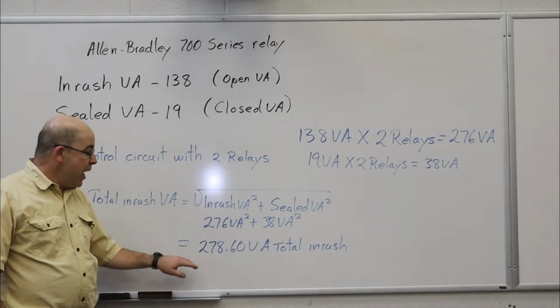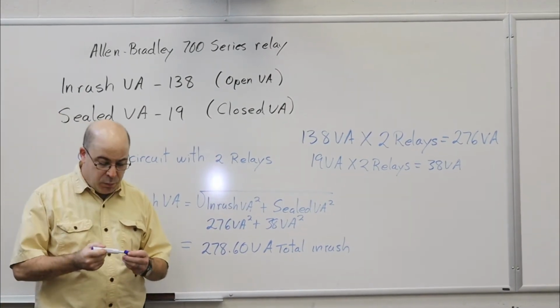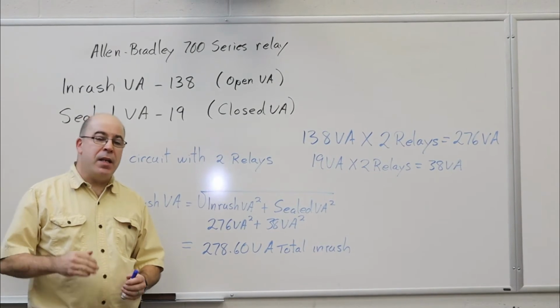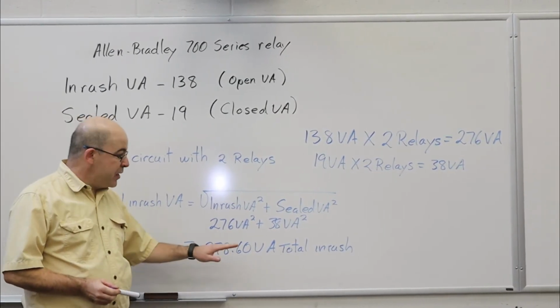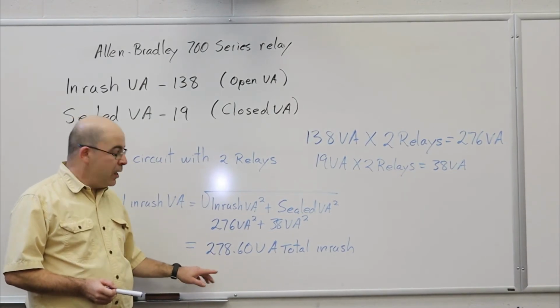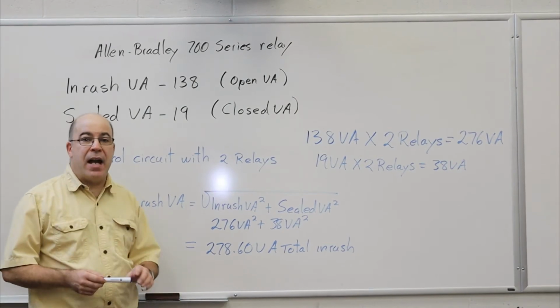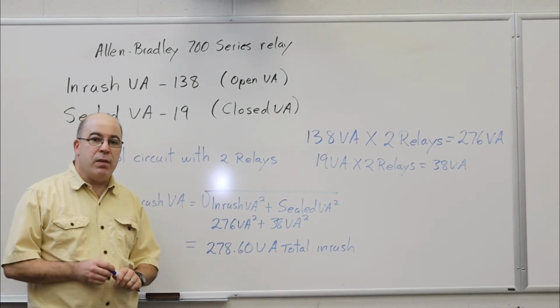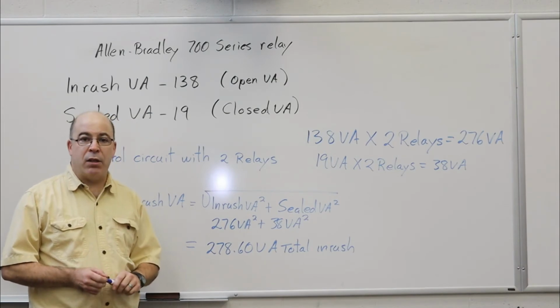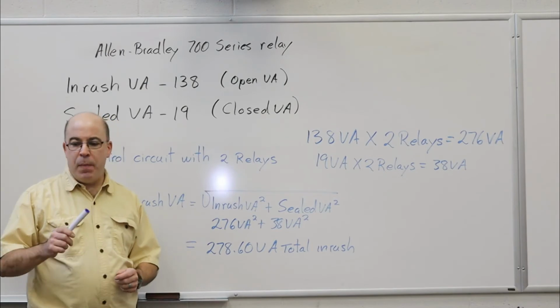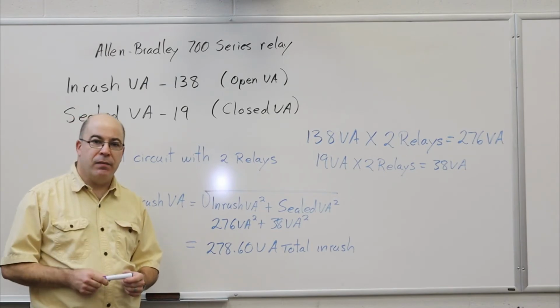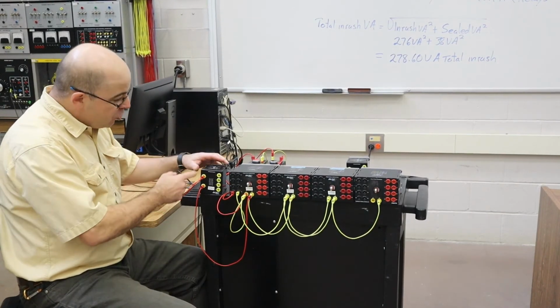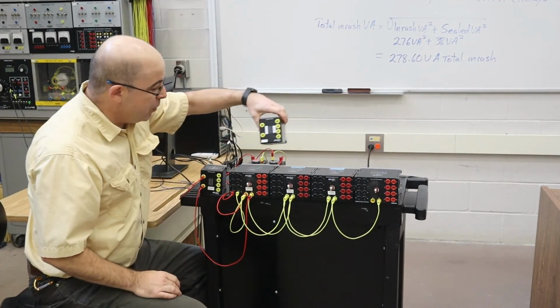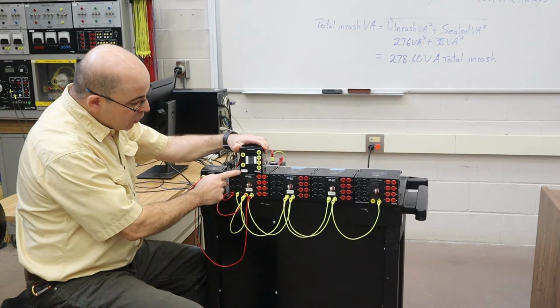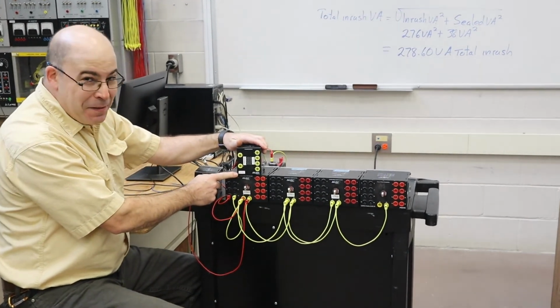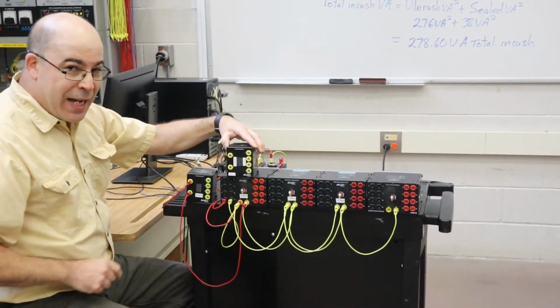Now that I have this value, I just need to consult one of the technical charts provided to us by the control transformer manufacturer to see which one of the control transformers is going to provide us with the appropriate amount of power to meet our needs. Now, I've already done some of this work beforehand, and I know that the 50 VA transformer will be more than adequate for this task. So now that we've done that, let's go back and actually build the circuit and put it to the test. So what we're going to do now is exchange the 25 VA transformer for the 50 VA transformer right here. And indeed, I've actually taken the opportunity to have all of the 50 VA transformers properly labeled to avoid any mistakes in our labs.